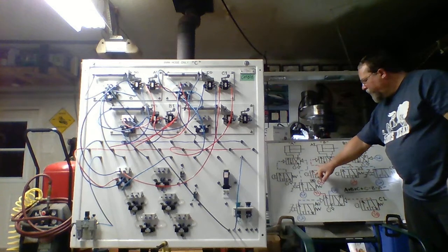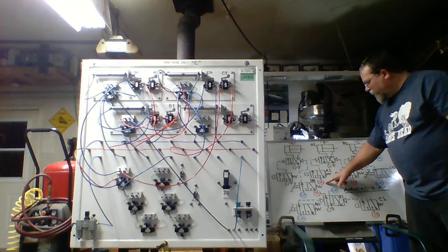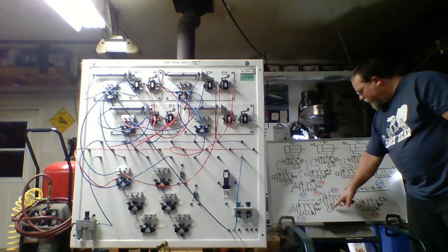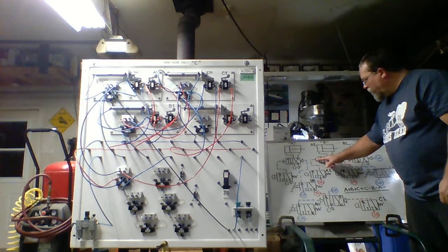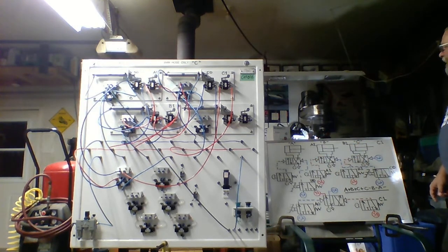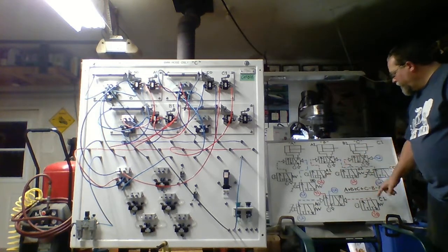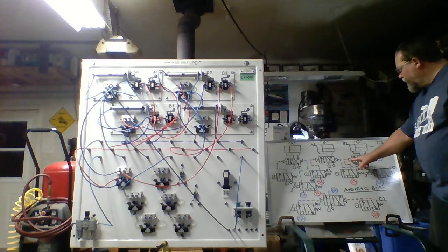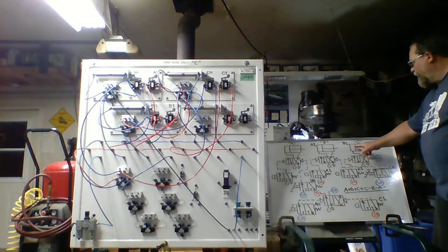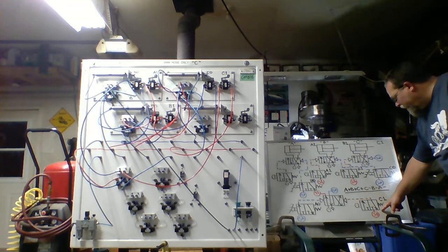Looking at A1 here, we have a cam activated 3/2 way, normally closed, spring return. Source 1 is what's available now, as shown here with your cascade valve. We open the flow path, that'll pilot the 4/2 way, which will charge the blind end for B and have that extend. And when cylinder B extends, it gets on B1. We show B1 here, which is set up the same as A1. We open the flow path here, pilot the 4/2 way for C, again charging the blind end, C extends. So when C extends, it gets on C1, which is down here on the bottom right.